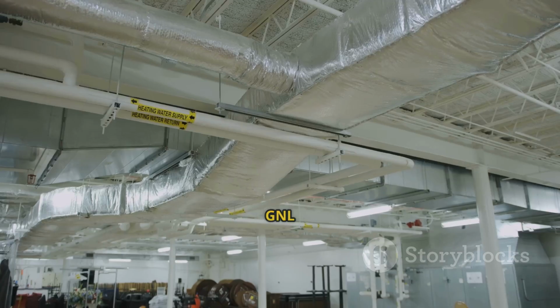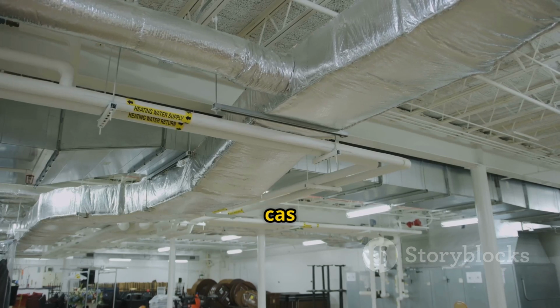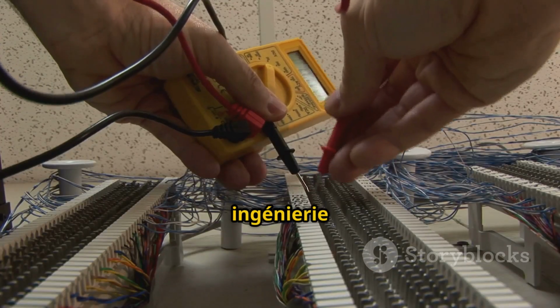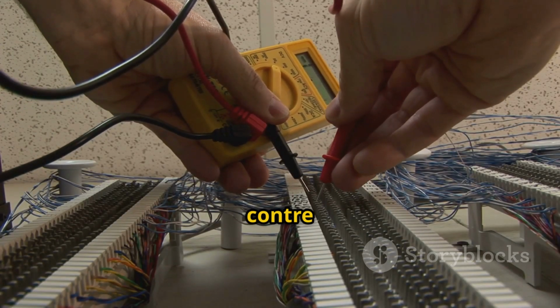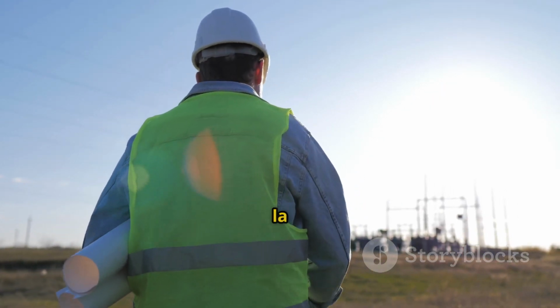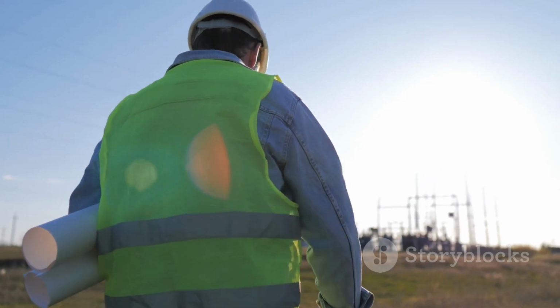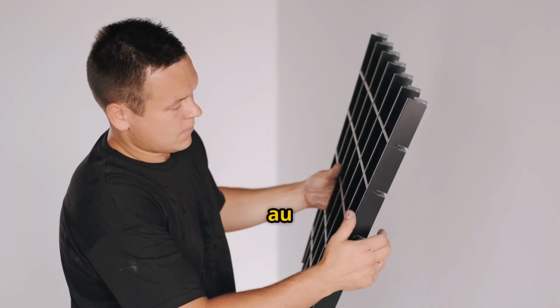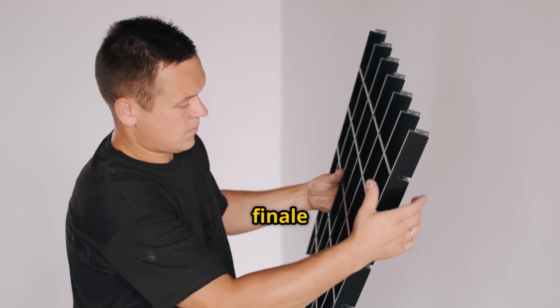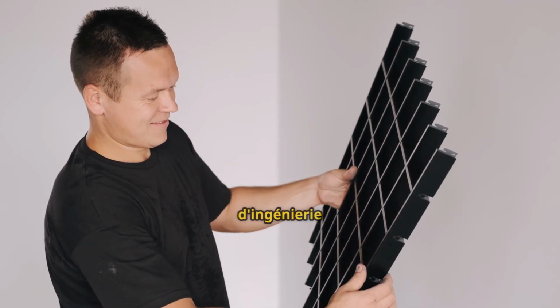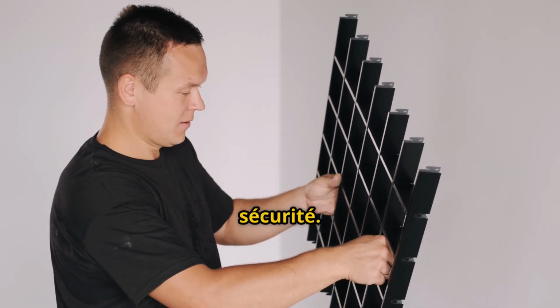The ladder tray design is non-negotiable in this high heat environment. Its open structure provides the maximum possible ventilation, allowing cooling breezes to flow freely around the power cables. This is critical for maintaining the ampacity, or current carrying capacity, of the cables. Engineers must perform detailed calculations that account for the solar loading, the direct heating effect of the sun on the trays and cables. To mitigate this, trays are sometimes installed with ventilated covers. These covers provide a shield from direct sunlight while still allowing hot air to escape through the vents, creating a chimney effect that enhances natural convection and cooling.